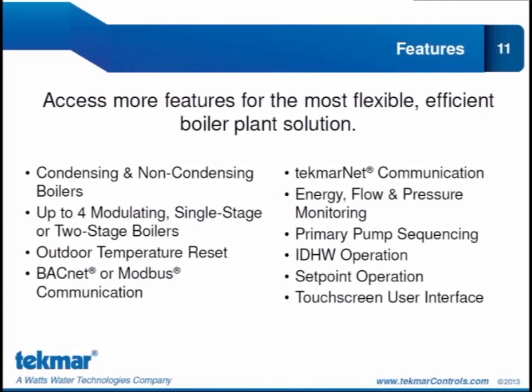The 284 has more features for the most flexible, efficient boiler plant solution, and we're going to look at 10 of those new features in this presentation. We'll start with the specialized control logic that the 284 has to operate up to 4 condensing and non-condensing boilers, be them modulating, single stage or two-stage. The 284 can treat each boiler differently, and we'll look at how it does that. Outdoor temperature reset is one of the applications that this control features. If this isn't the type of application that you have, we'll also look at how you can configure the control to do something else. BACnet or Modbus communication.